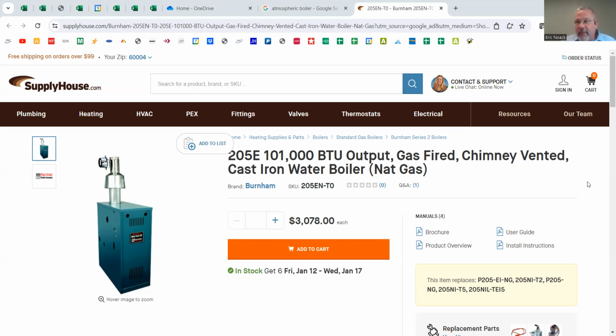So thinking back, when you talk about old boilers, one of the most common things with boilers is oversizing. They oversize boilers a lot. It's very common. And in a limited way, it doesn't cause too much problem, except it's less efficient and it costs them more for the bigger boiler that they're not even able to use. When it gets to an extreme, though, it'll do that sooting thing that I talked about previously when I talked about that bypass. So the boiler will soot up if it's way oversized.